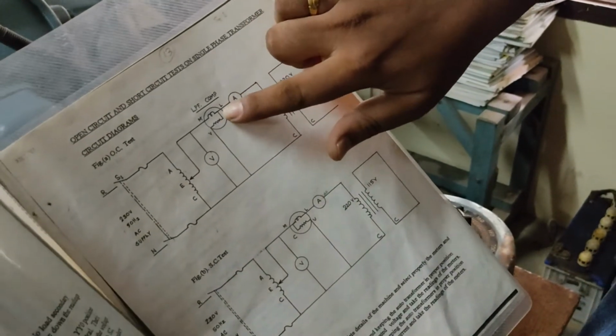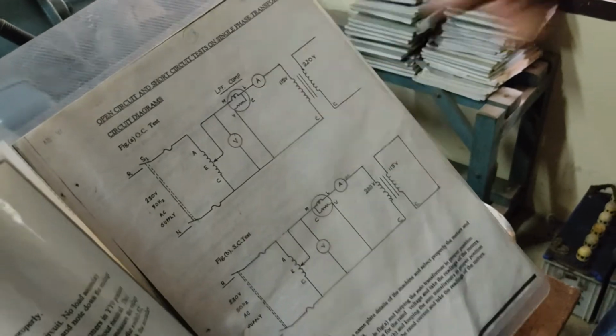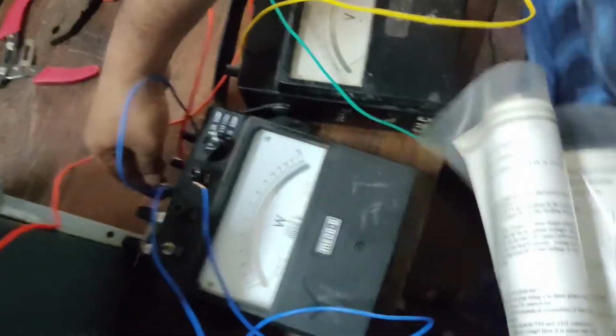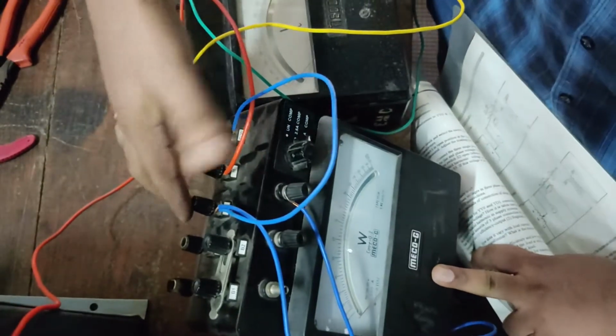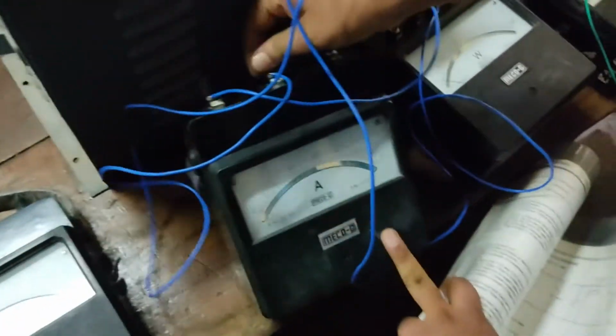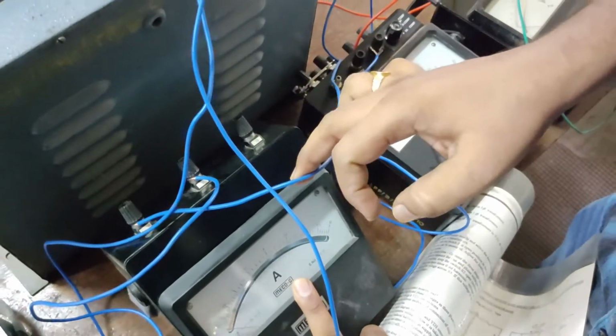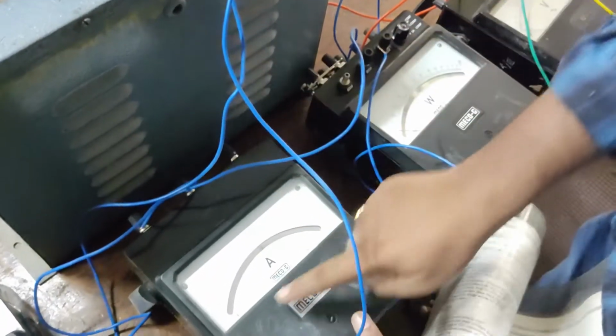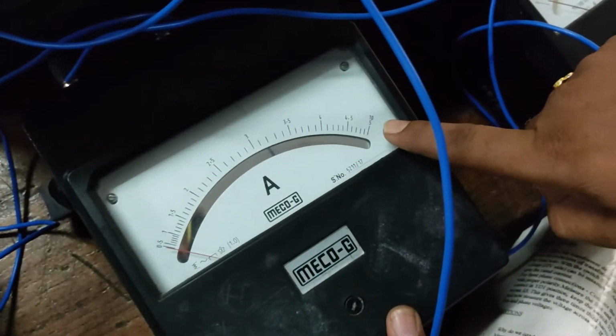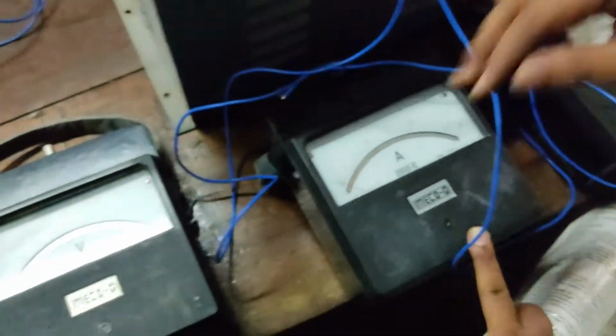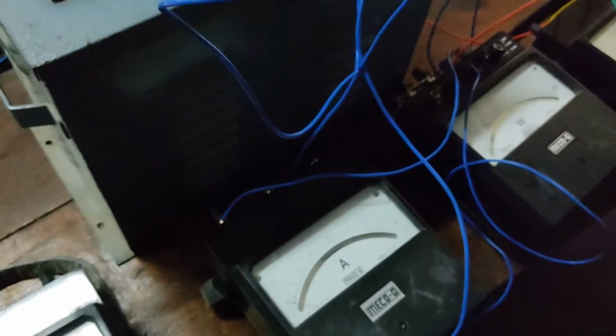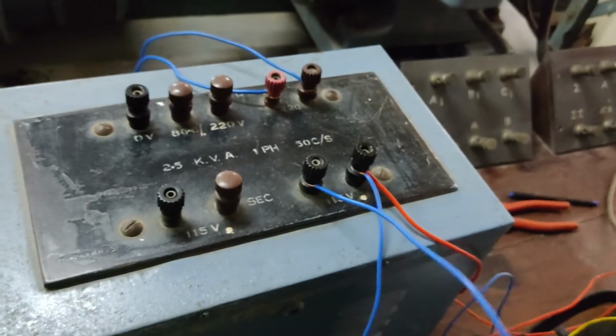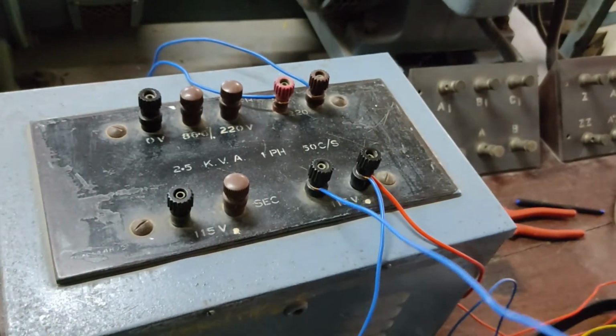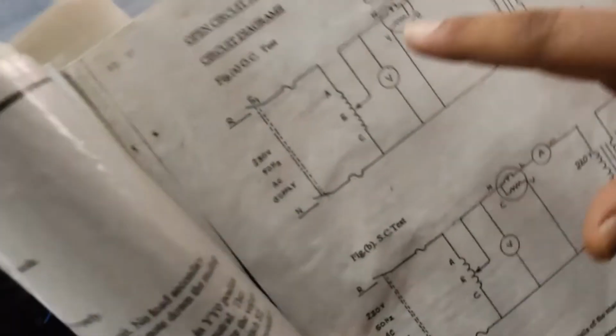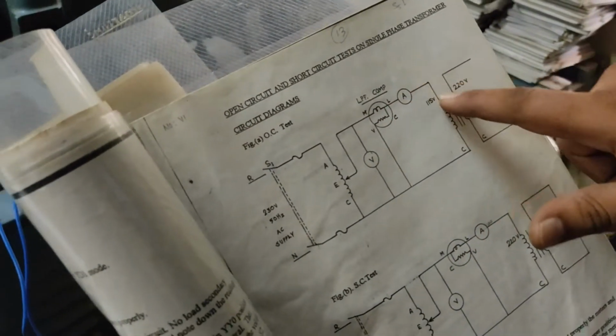Next, the L terminal has been connected to one terminal of the ammeter. The ammeter which I have used is 0 to 5 amperes. The other terminal of the ammeter has been connected to the neutral terminal of the other side of the transformer. Okay, this connection is over.